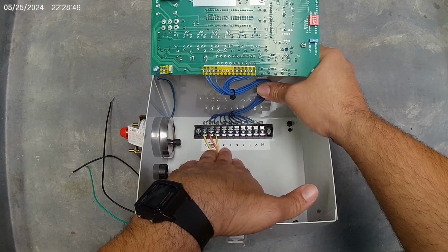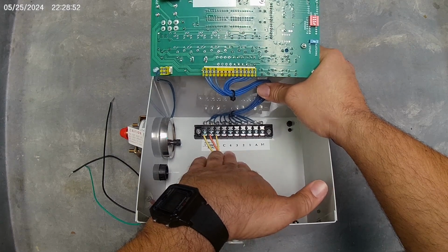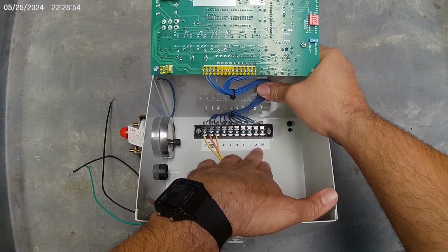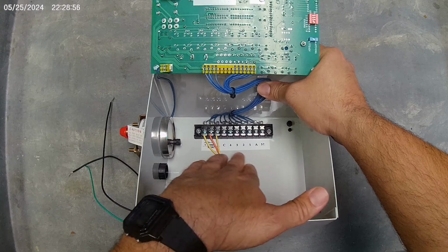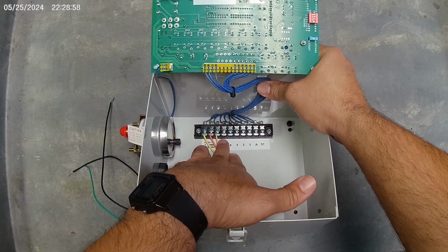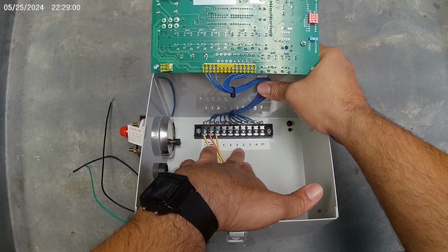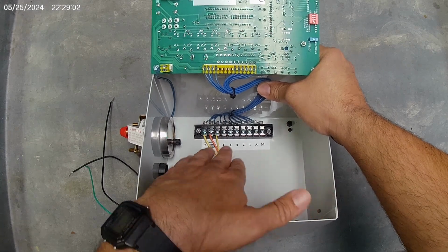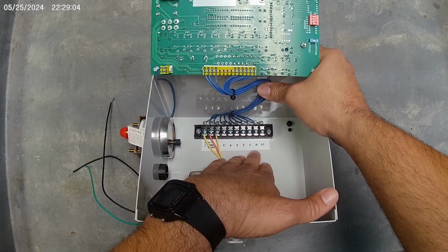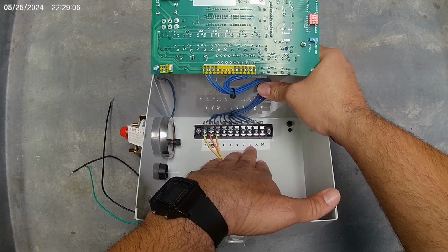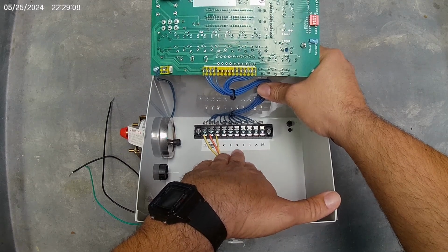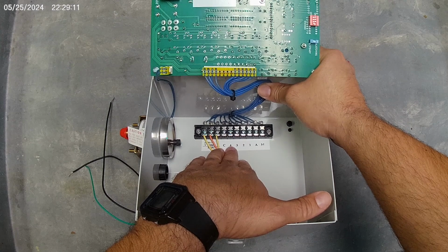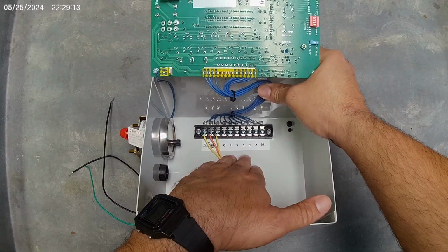We have a single common, our individual solenoid outputs for the individual filters, an alarm, and a master. And one wire from each solenoid would go to common and then to its corresponding other terminal. This is a 4-station controller, but if we only had 3 filters, you would wire to 1, 2, and 3 and leave 4 open, and we'll go over the programming of that later.